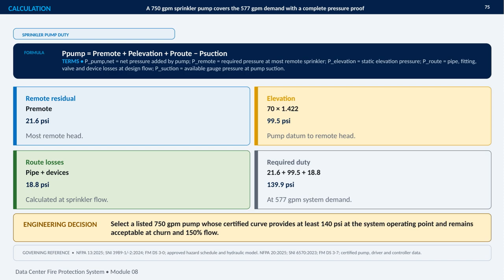The engineering decision is to select a listed 750 GPM pump that can provide at least 140 psi at this operating point. The certified pump curve must also remain acceptable at churn and at 150% flow. This selection is governed by the cited NFPA, SNI, FM, hazard schedule, hydraulic model, and certified equipment requirements.